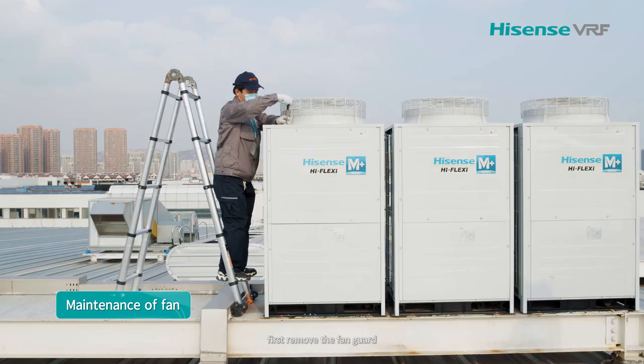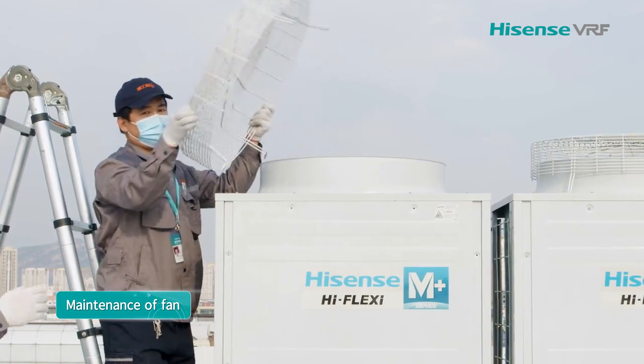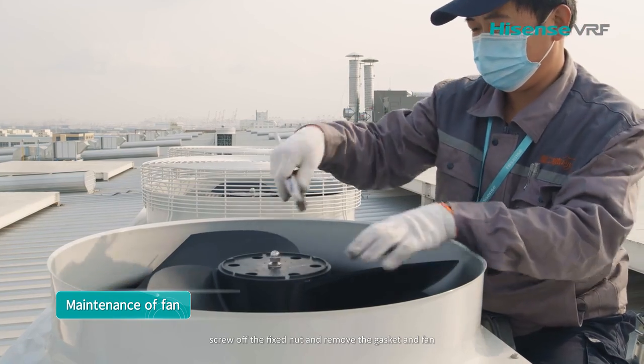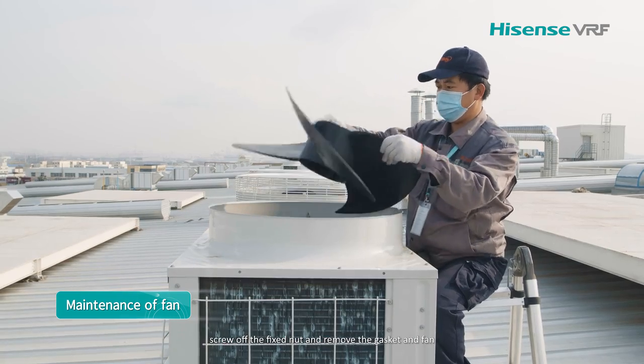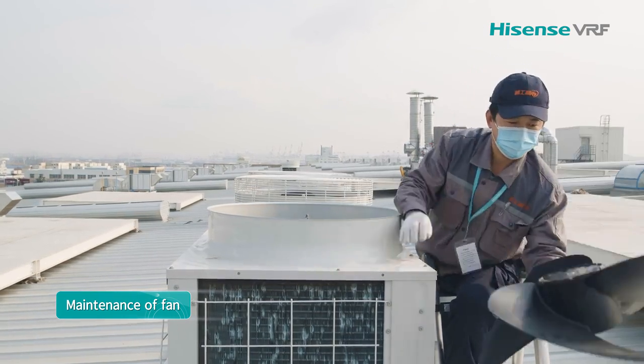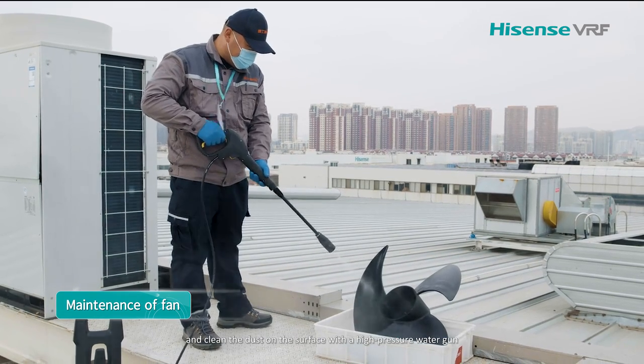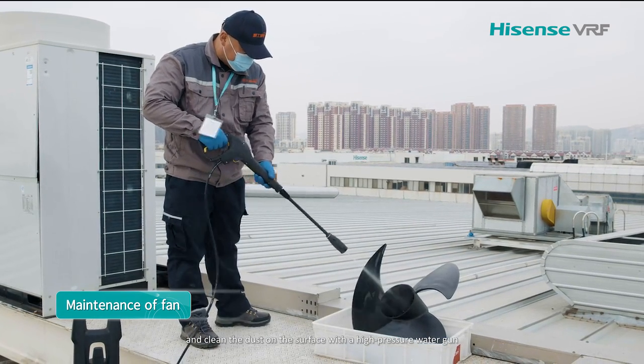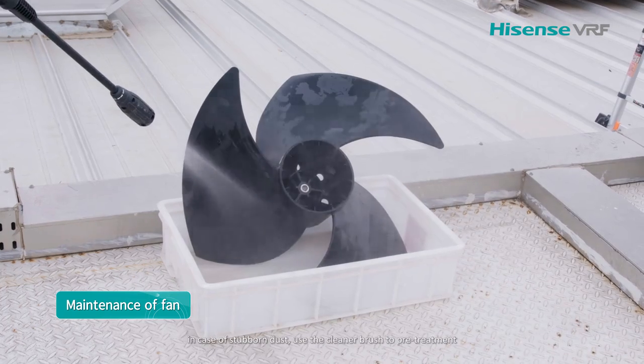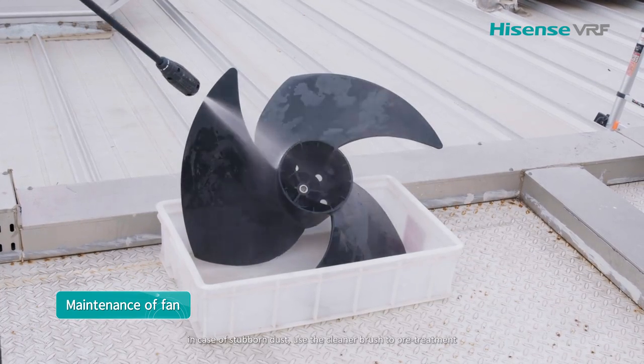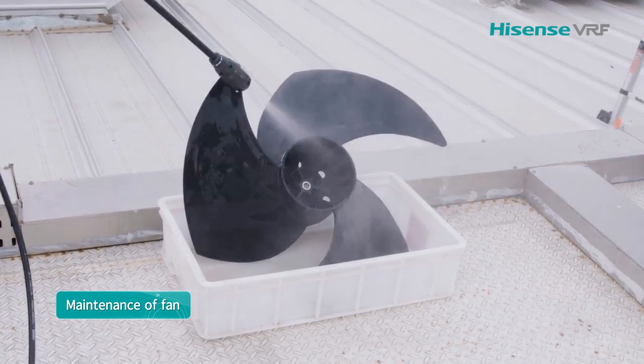First, remove the fan guard. Screw off the fixed nut and remove the gasket and fan. And clean the dust on the surface with a high-pressure water gun. In case of stubborn dust, use the cleaner brush to pre-treatment.